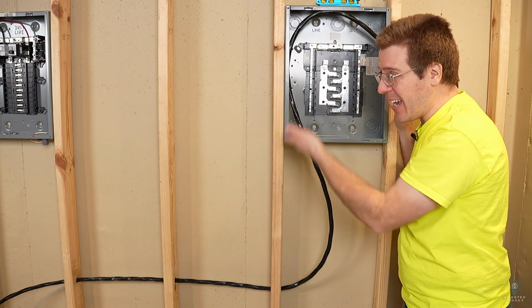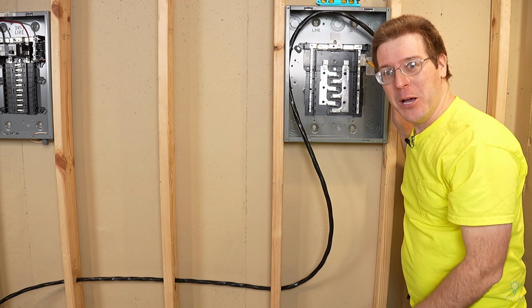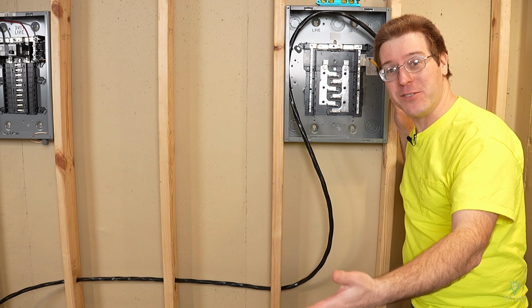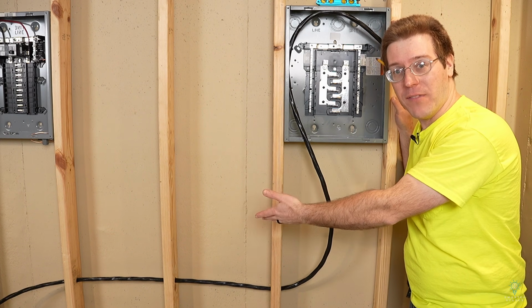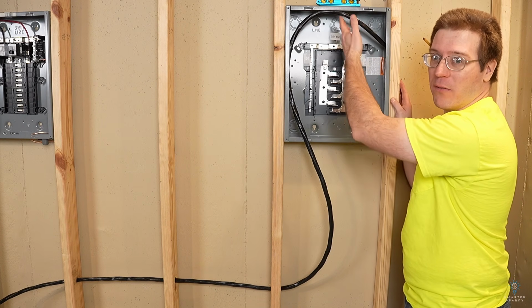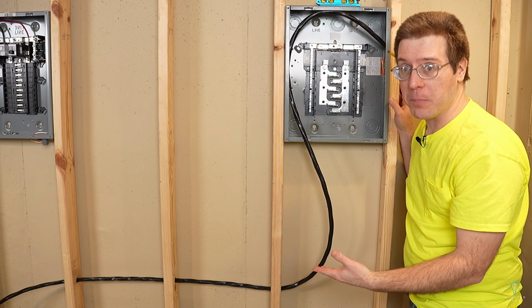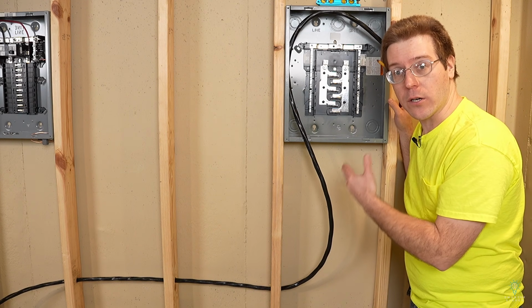And now in this case, you know, maybe I've wasted 10 feet. But in the real world, you might have just wasted a 100-foot run of that wire. So that extra 12 inches that you leave in the panel, it's cheap insurance. Don't cut your wire too short.